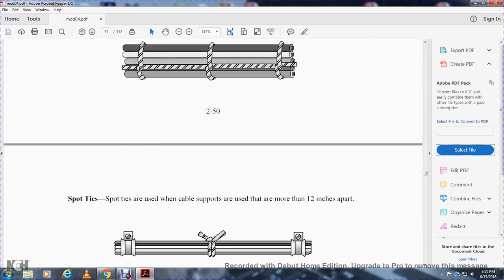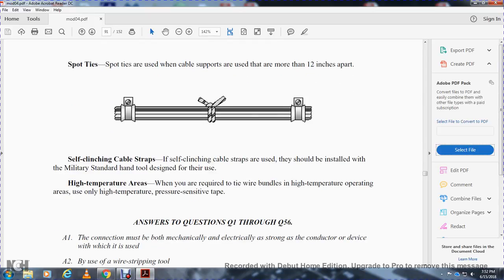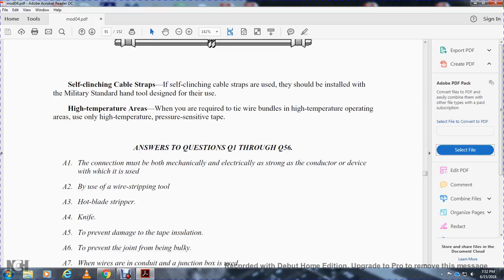Spot ties are used for cable support, spaced more than 12 inches apart. Self-clinching cable straps should be installed with military standard hand tools designed for their use. In high temperature areas, when use is required to tie bundles in high temperature operating areas, use only high temperature pressure-sensitive tape. And that is the summary for Chapter 2.